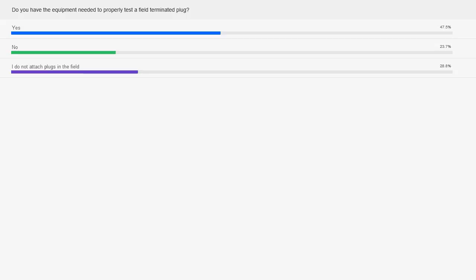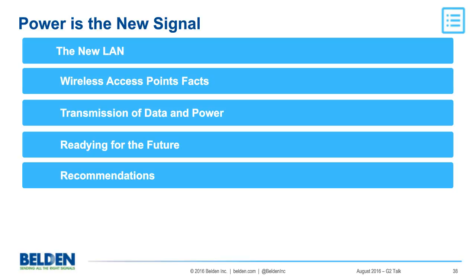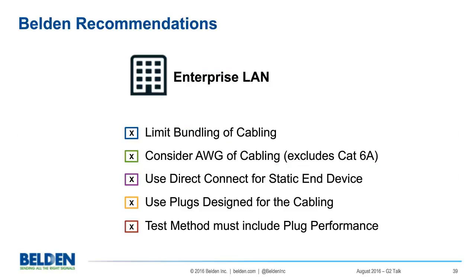All right, so lastly, I'd like to go over some recommendations, just kind of a review of what we talked about. So the recommendations, first off, limit the bundling of cabling. With PoE, you're going to have current going through the cables. Current through cables brings out what are called I2R losses. This is the power loss because of the resistance in the cabling. When lots of cables are brought together in a large bundle, the cable on the inside can't dissipate the heat, and so it becomes trapped, and it makes it hotter. This causes insertion loss issues, and also causes your DC resistance to go up, which also affects your power delivery efficiency.